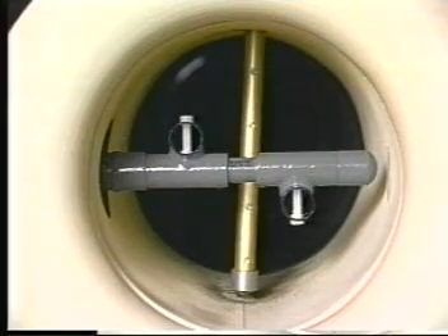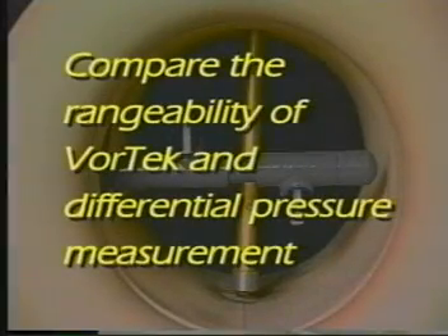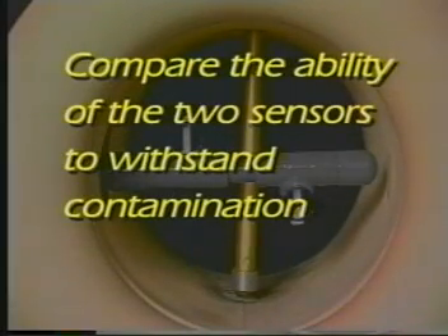Here, the vortex sensor and the traditional Pitot sensing system are mounted together in a test duct for a two-fold comparison. First, we'll compare the rangeability of vortex and differential pressure measurement by reducing flow velocity. Then, we'll compare the ability of the two sensors to withstand contamination.